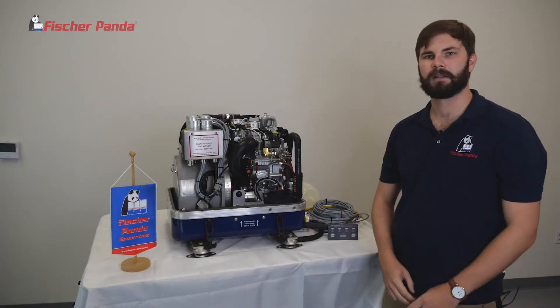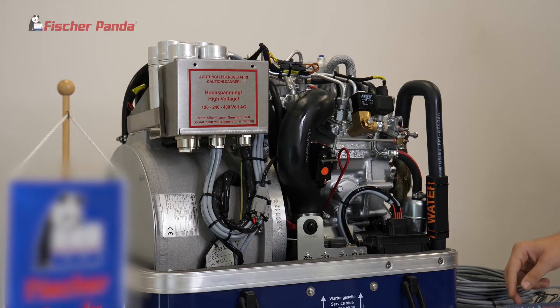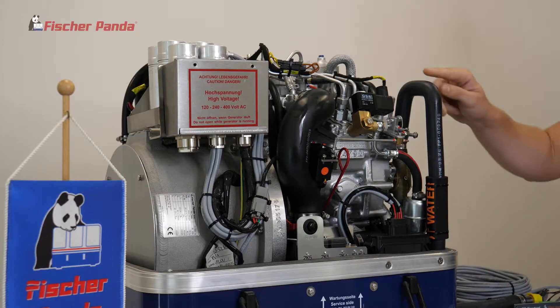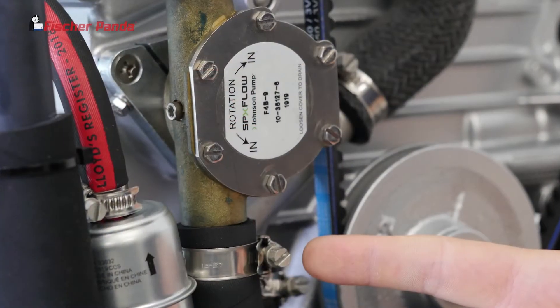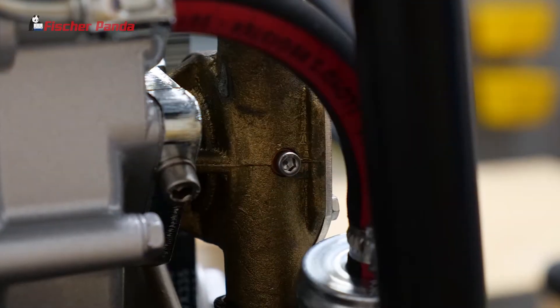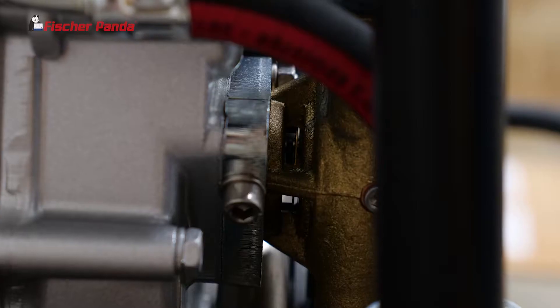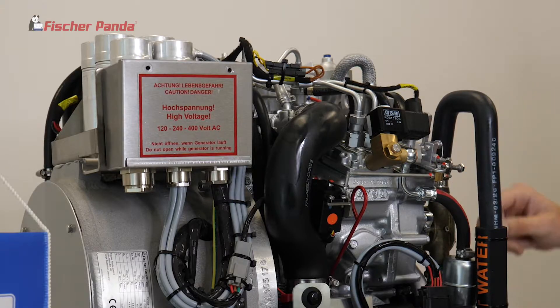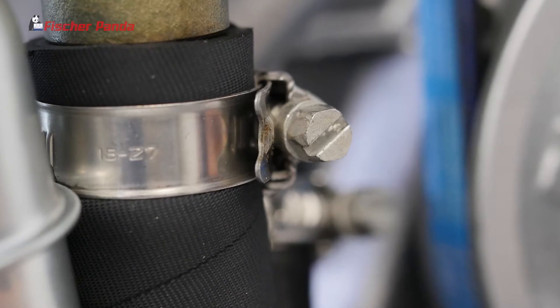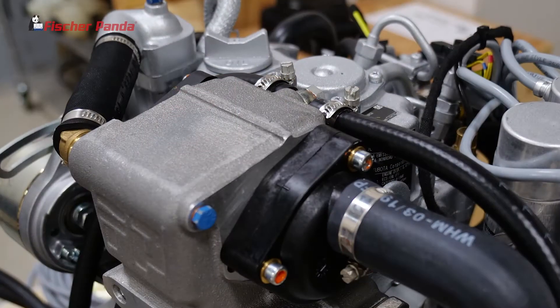Next, we're going to check the raw water system. Start with the inlet to the generator and work our way up to the inlet to the water pump. Check the cover of the water pump for any leaks. Check the cam screw. Check the seal on the back side of the pump. Check the hoses that lead to your siphon break loop. From there, we'll go up and check the hose clamp on the heat exchanger.